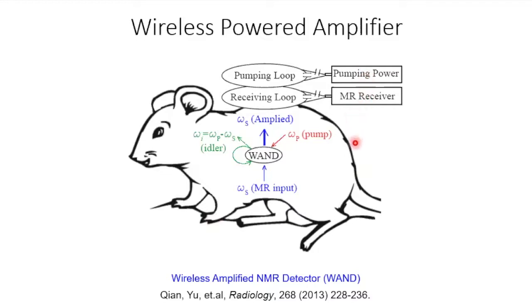So this is a little bit more detail about operation principles. Suppose we have a weak MR signal at the frequency of omega S, and suppose we have a strong external pumping signal at omega P. And suppose the device can perform some nonlinear interaction to enable the weak MR signal to exchange energy with the external pumping signal. After energy exchange, they will generate a signal at a different frequency, which we called the idler signal. We called it the idler signal because this signal is not directly detected. Instead, it will mix back with the pumping signal and generate a secondary amplified signal at the original MR frequency.